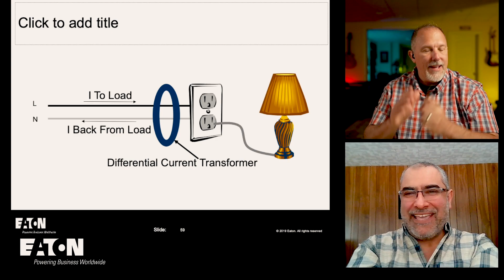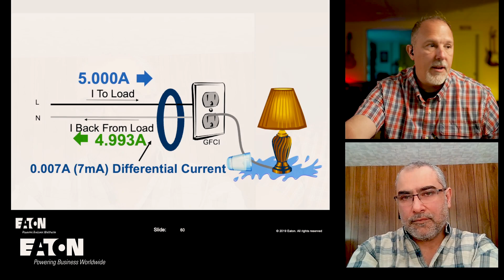Very important, because you would cancel the whole thing. So anytime current flows outside of that path, it's the difference of current - whatever goes out on the hot, you subtract what comes back on the neutral, and the difference means it's going somewhere else. If that difference is greater than 6 milliamps - it can't trip less than 4, has to trip after 6 - anything greater than 6 milliamps, it's going to open. It doesn't know where it went, it just knows current is going somewhere outside of the normal current carrying path.